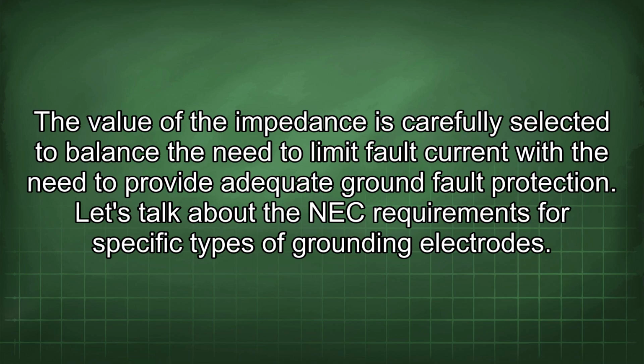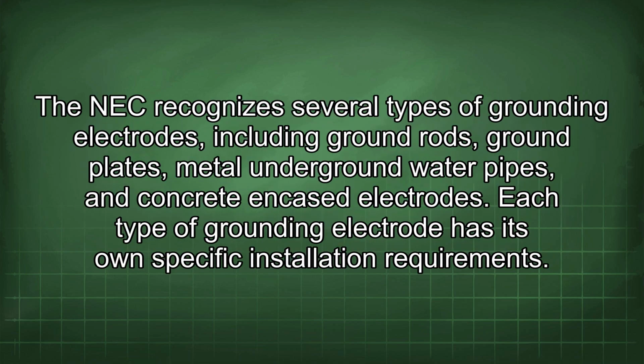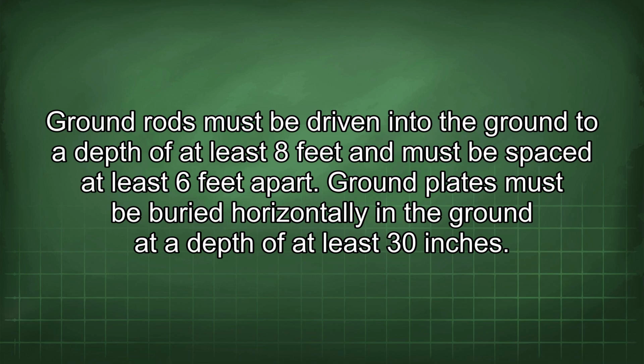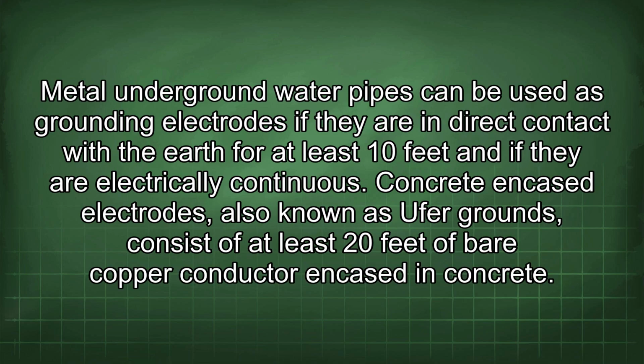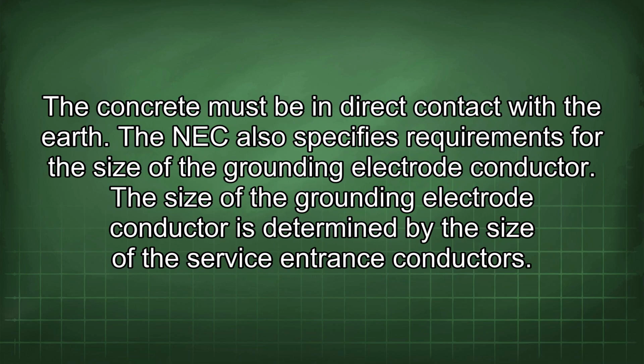Let's talk about the NEC requirements for specific types of grounding electrodes. The NEC recognizes several types of grounding electrodes, including ground rods, ground plates, metal underground water pipes, and concrete encased electrodes. Each type of grounding electrode has its own specific installation requirements. Ground rods must be driven into the ground to a depth of at least 8 feet and must be spaced at least 6 feet apart. Ground plates must be buried horizontally in the ground at a depth of at least 30 inches. Metal underground water pipes can be used as grounding electrodes if they are in direct contact with the earth for at least 10 feet and if they are electrically continuous. Concrete encased electrodes, also known as Ufer grounds, consist of at least 20 feet of bare copper conductor encased in concrete. The concrete must be in direct contact with the earth.